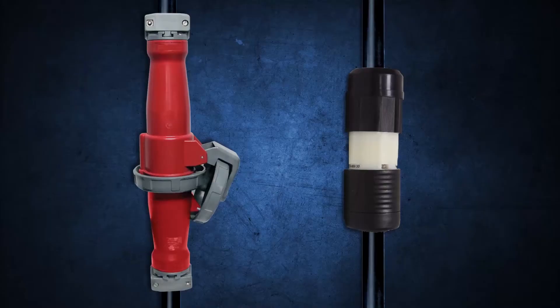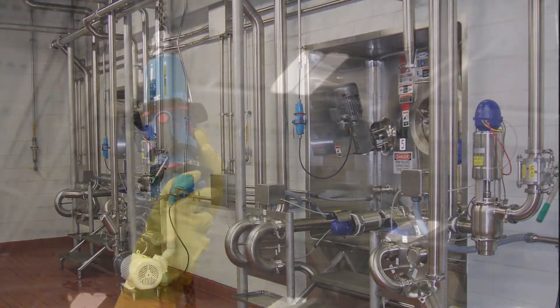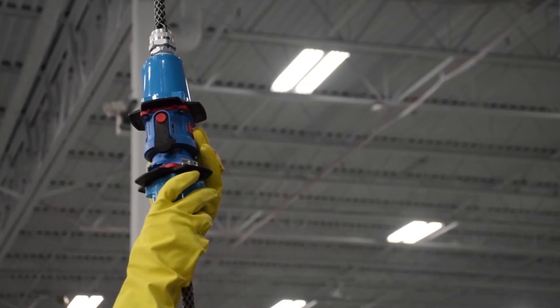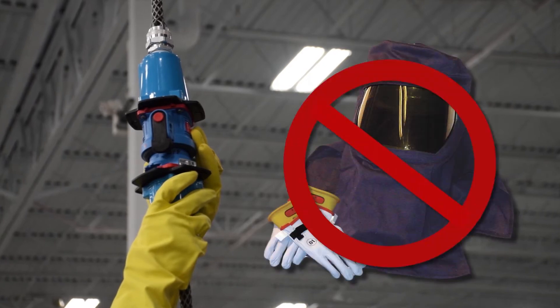Meltric switch rated plugs and receptacles protect against arc flash and help facilities comply with NFPA 70E or CSA Z462 electrical safety standards. Connection or disconnection of the plug is considered an NFPA 70E-defined normal operation, so PPE is not required.